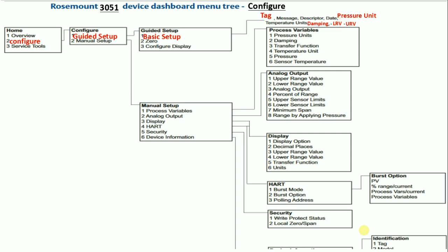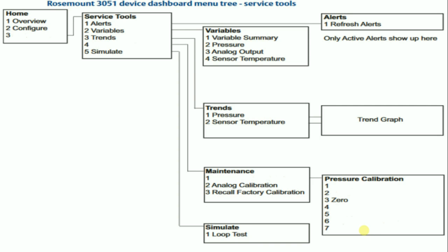Now we will see how to calibrate a 3051 pressure or differential pressure transmitter. For calibration, go to service tools under home, then go to maintenance, then under maintenance go to pressure calibration.